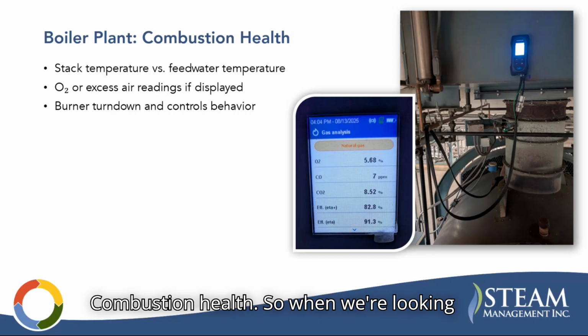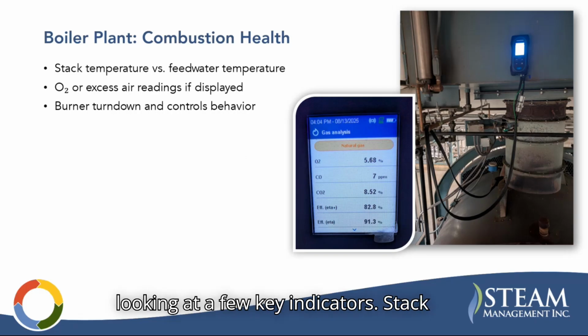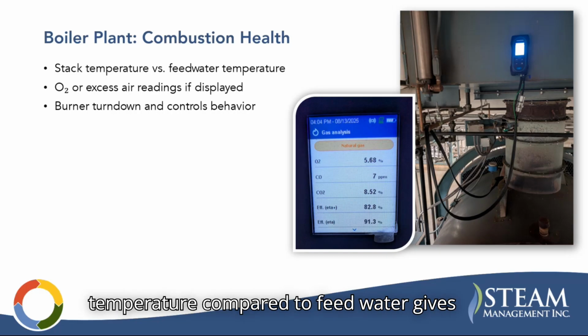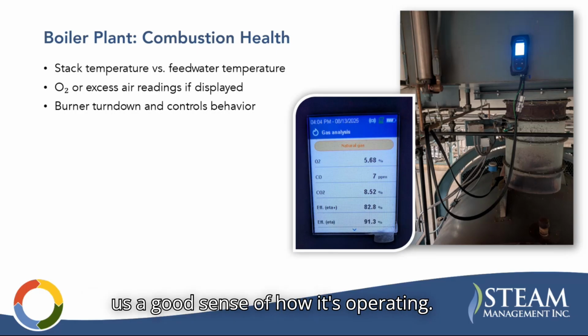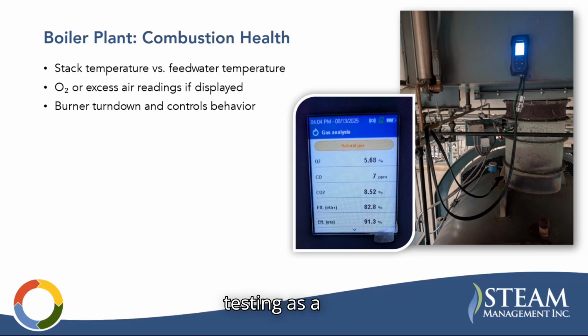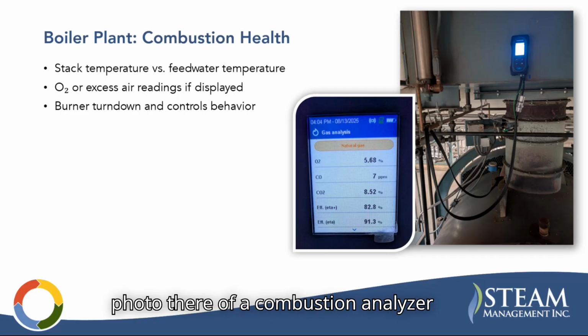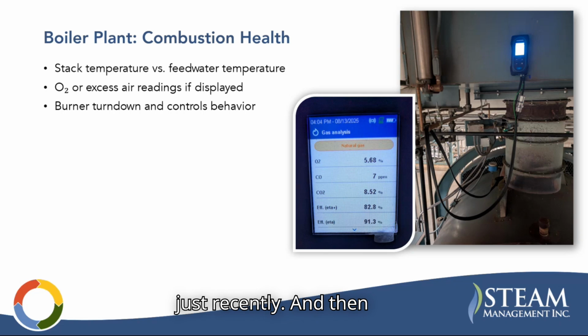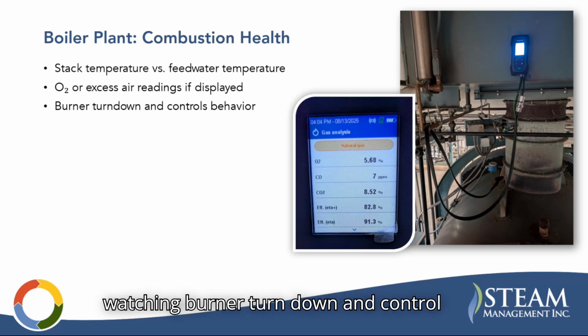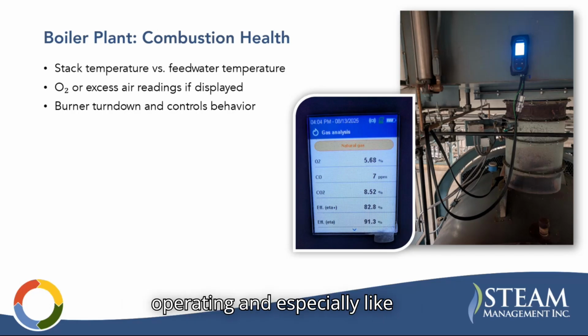Combustion health. When we're looking at boiler combustion health, we're looking at a few key indicators. Stack temperature compared to feed water gives us a good sense of how it's operating. You have O2 or excess air readings, which you can do through combustion testing. There's a photo there of a combustion analyzer from a test we did just recently. And then watching burner turn down and control behavior tells us how the boiler's operating, especially across its load profile.